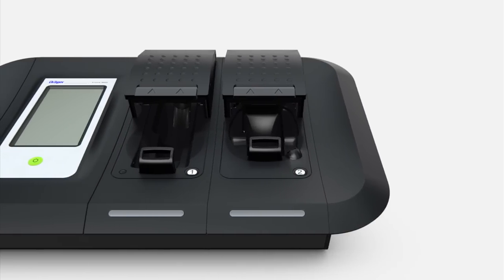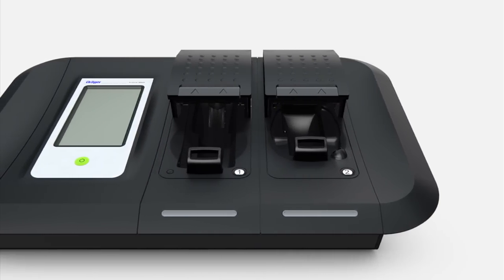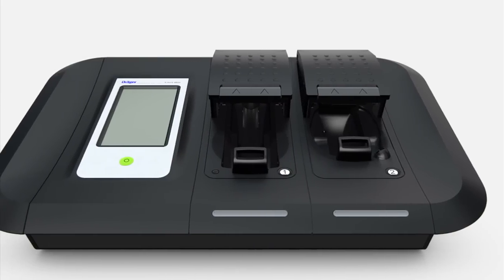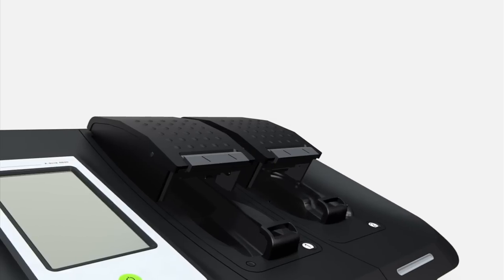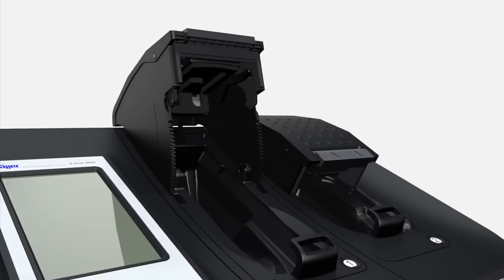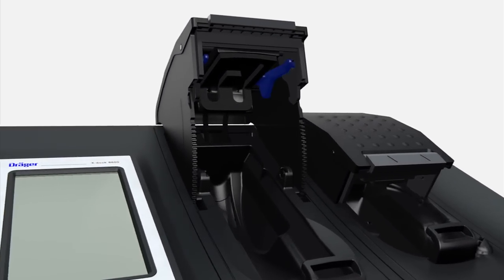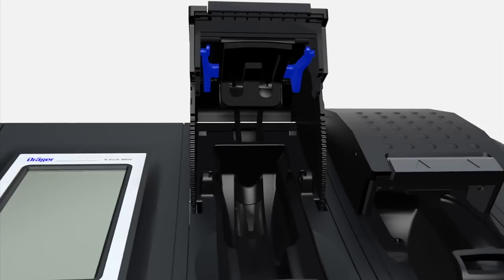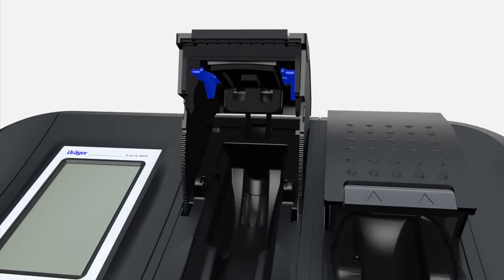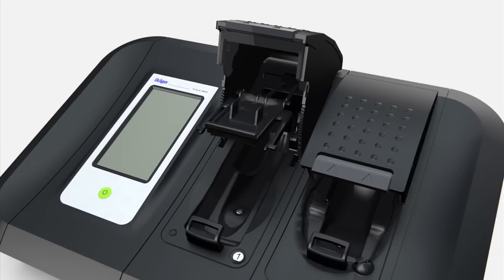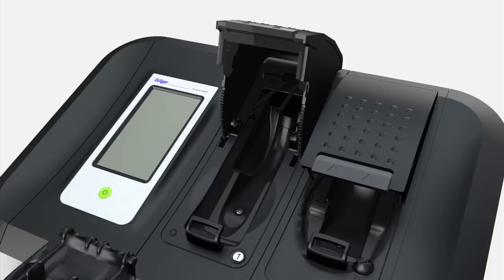The sealing inserts of the module lid must be replaced as soon as the seal shows signs of wear. To do so, open the module lid. Push the outer locking lugs inwards and pull the sealing insert first downwards and then to the front. Remove the tubes and replace the sealing insert.